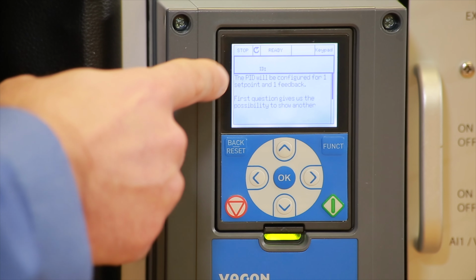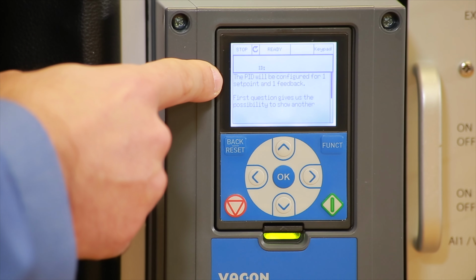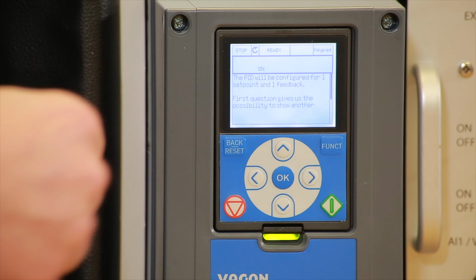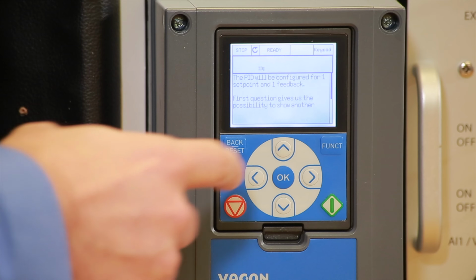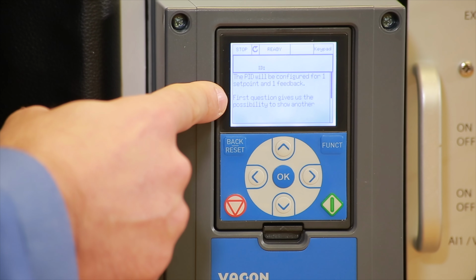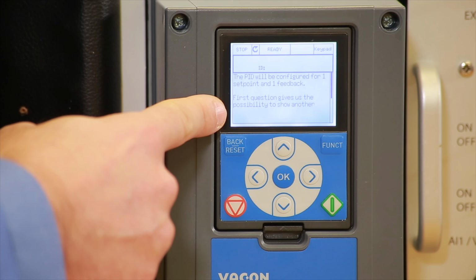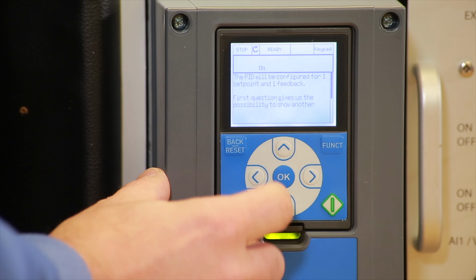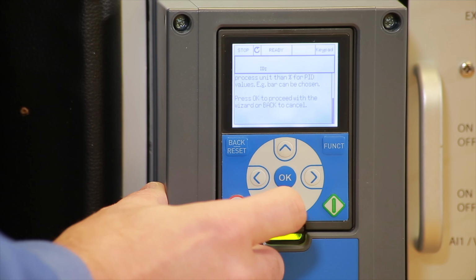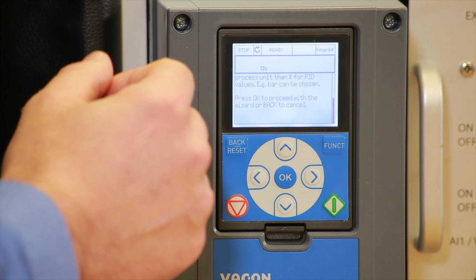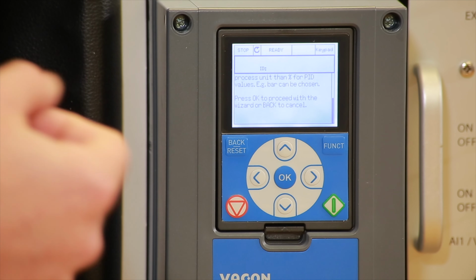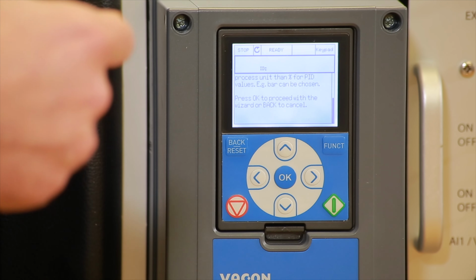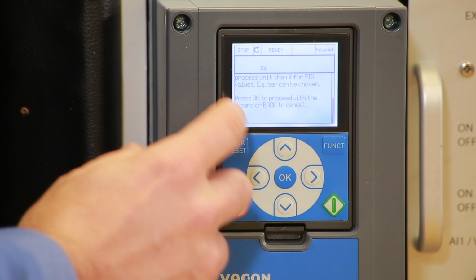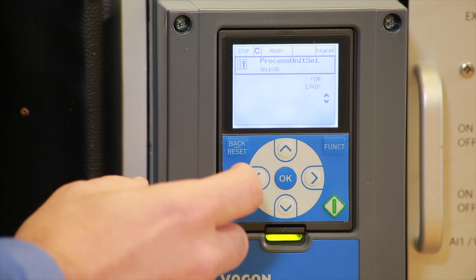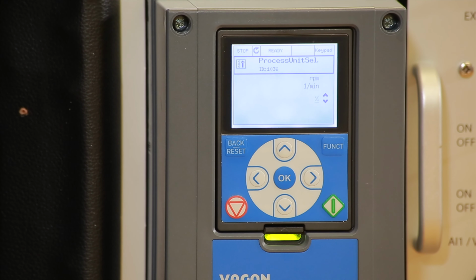The next thing, it says the PID will be configured for one set point. Remember, we have one pressure transducer, so one set point and one feedback. The first question gives us the possibility to show another process unit than percentage for PID values. Example, so this drive can display PID bars, you'll see shortly. So we're going to click OK, and we're going to select what we want to monitor on the screen.